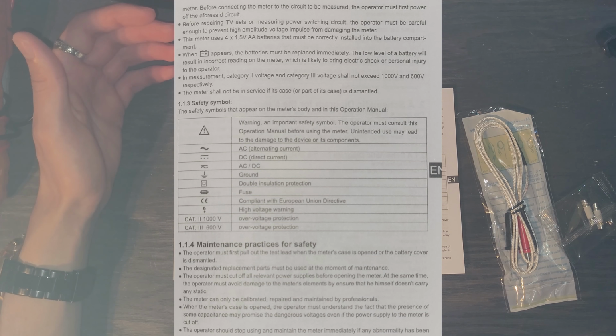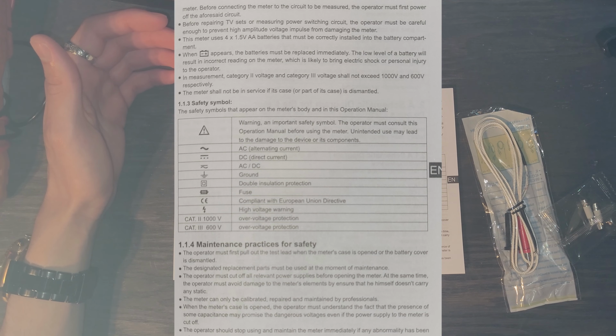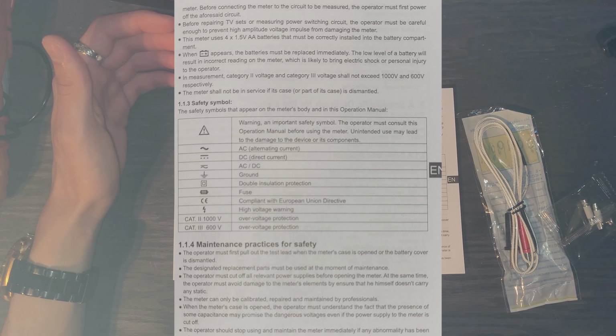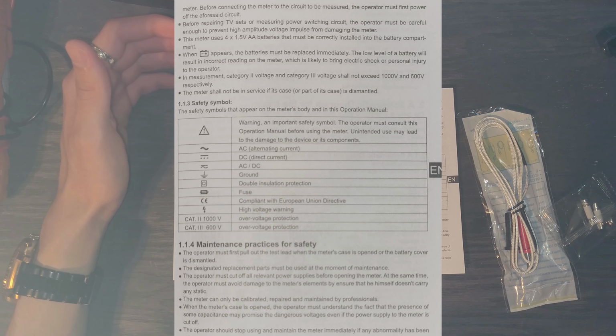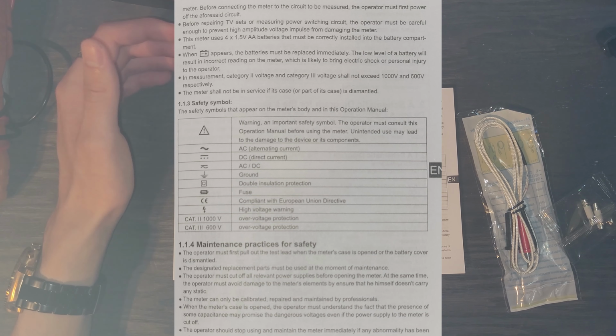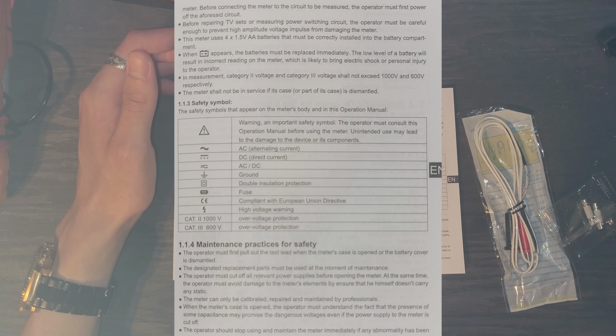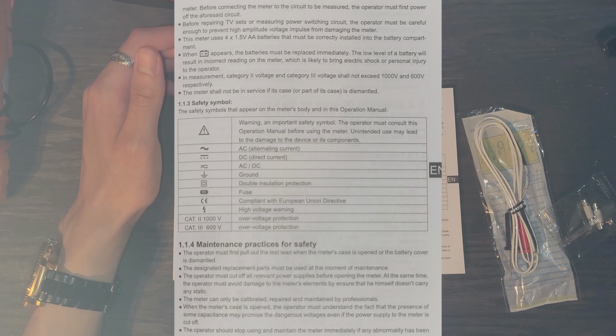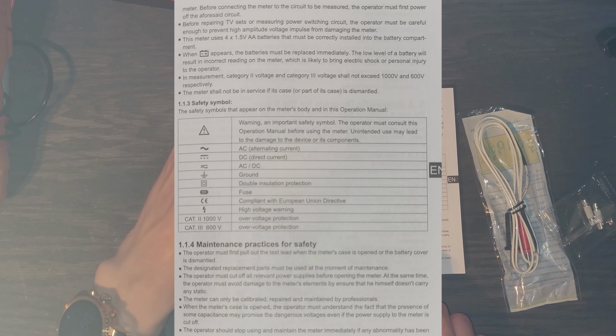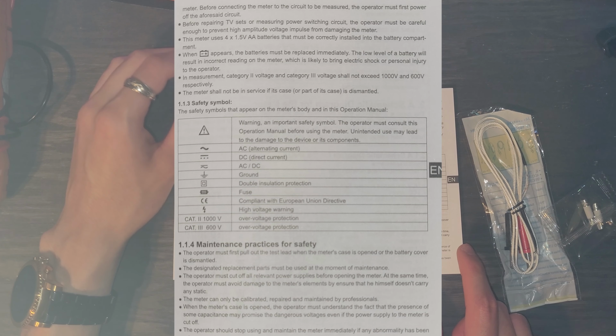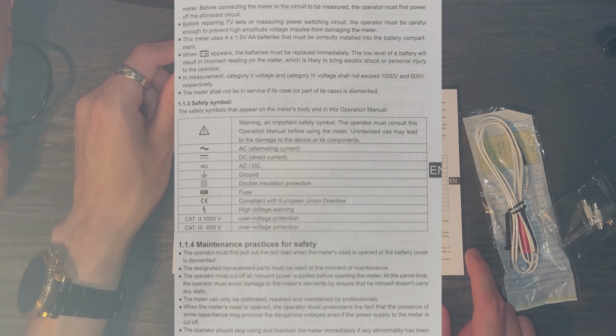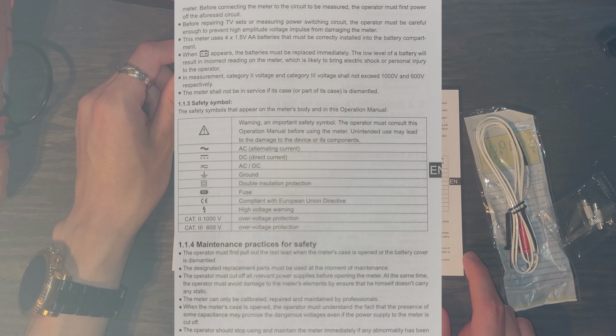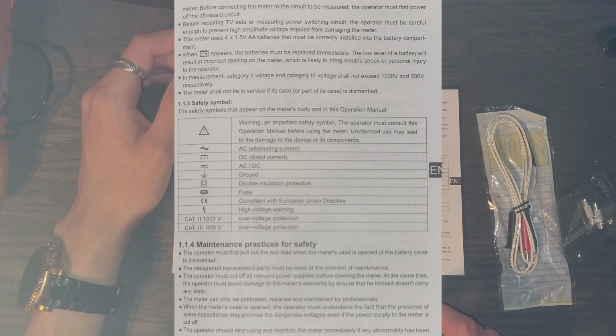Now we're going to look at maintenance and practices for safety. The operator must first pull out the test lead when the meter's case is opened or the battery cover is dismantled, so make sure everything is disconnected from an actual live circuit. The designated replacement parts must be used at the moment of maintenance. The operator must cut off all relevant power supplies before operating the meter. At the same time, the operator must avoid damage to the meter's elements by ensuring that he himself doesn't carry any static. So you don't want to interfere with the results or anything.